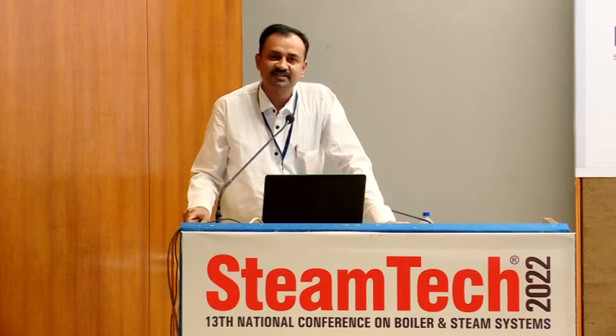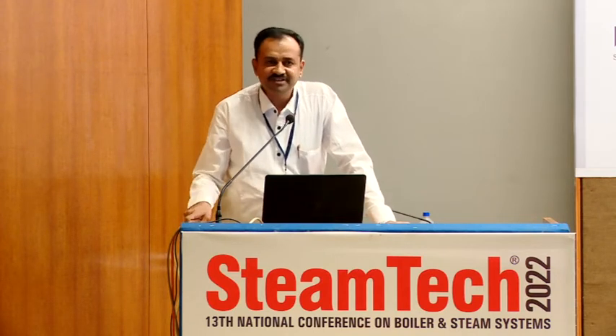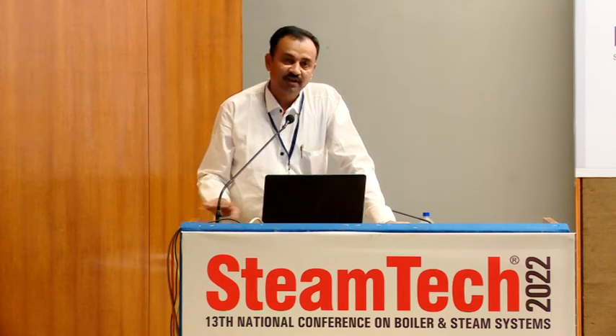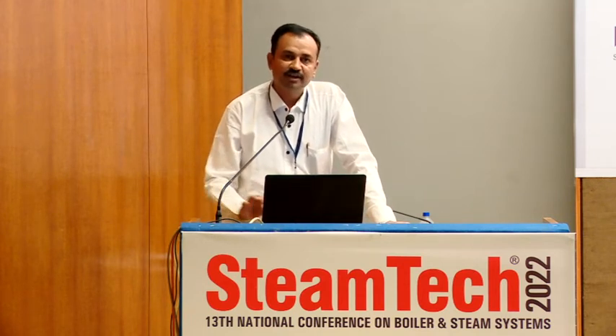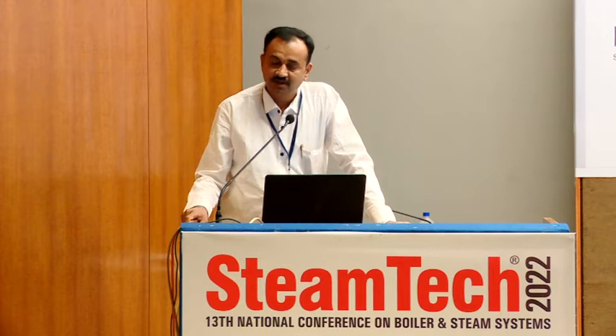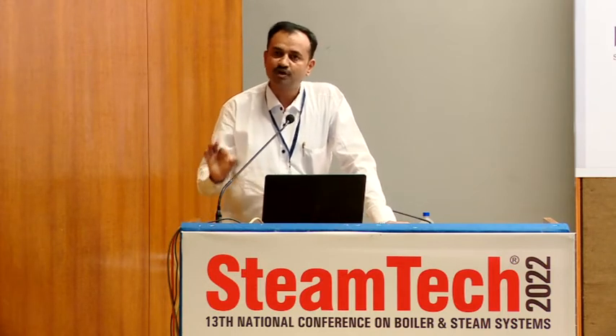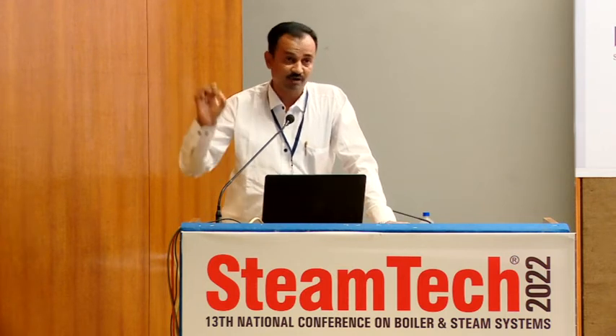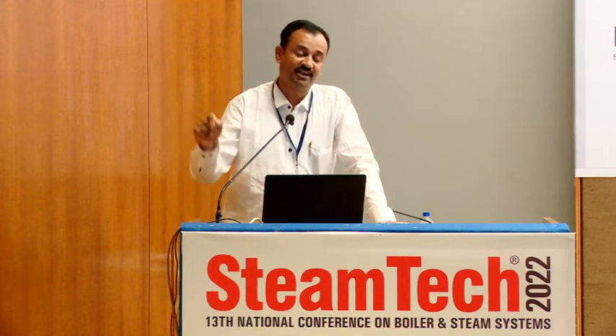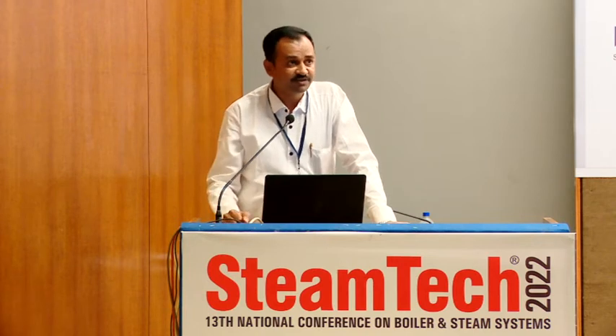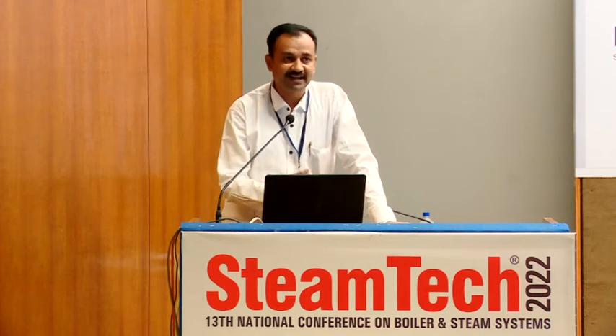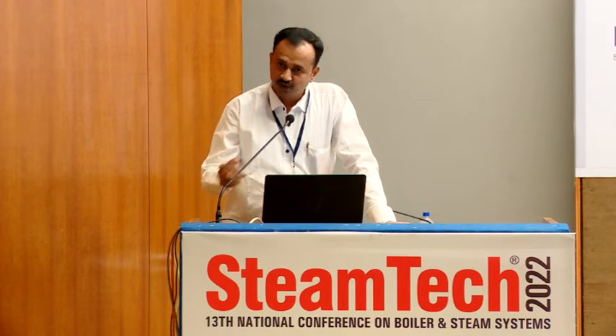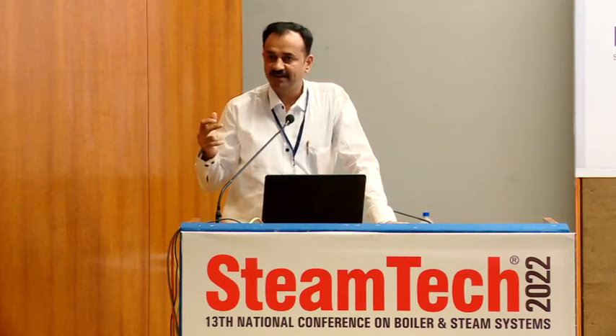So this is the way we suggest, and this is the way it has been done: efficiency and safety monitoring equipment installed in the boiler house, and with this you can get the equipment on the cloud. With this equipment on the cloud, we have thousands of energy audit reports available with us. So we can identify the sweet spot for that boiler house: what the operating condition should be, what the output set point or control variable for the ID FD feeder should be for that operating condition. And at the end, we can fire this set point back to the user and tell them you need to modify this set point by this percentage, and you need to narrow down your operating KPI. Operating KPI means steam to fuel ratio, indirect efficiency, and combustion parameters, which should be trimmed down such that you can get better efficiency and safety also.